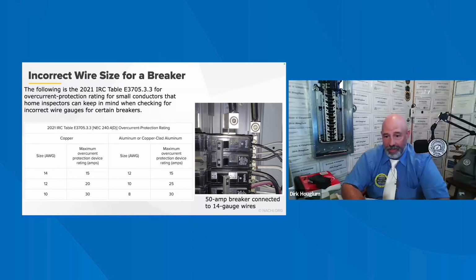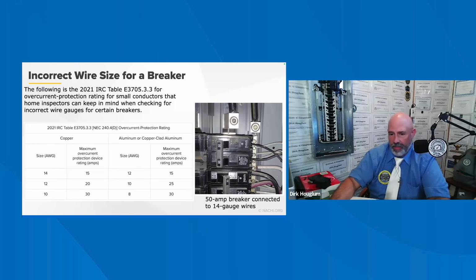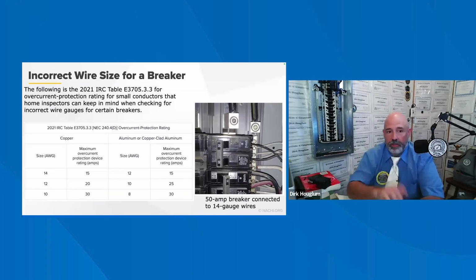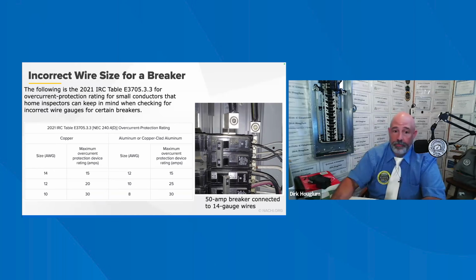Now there is a variance there when you're dealing with air conditioners, because they can actually be undersized as long as it doesn't go below the minimum amp size. And that's totally different. You can see that in the NEC. I think we have a, let's see. I think we got something in there. Can't think of where it's at in the NEC, but it is actually approved for that specific case. So there we go.